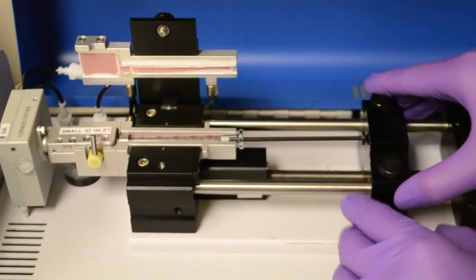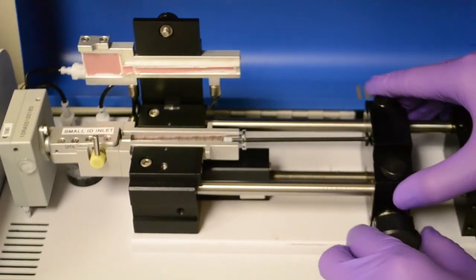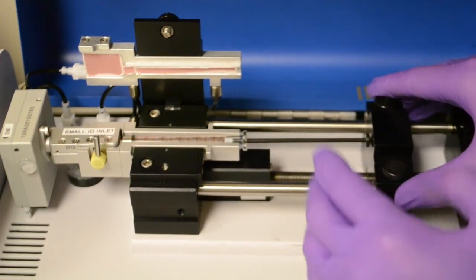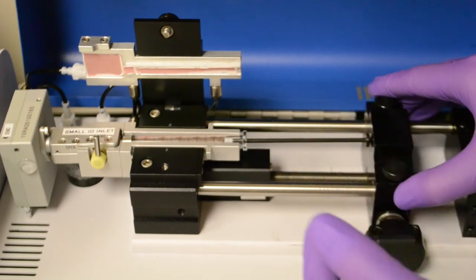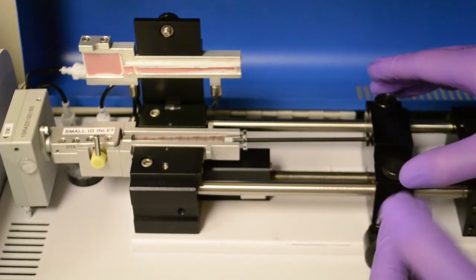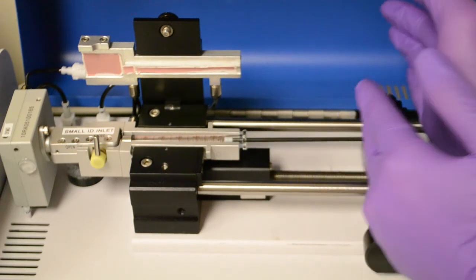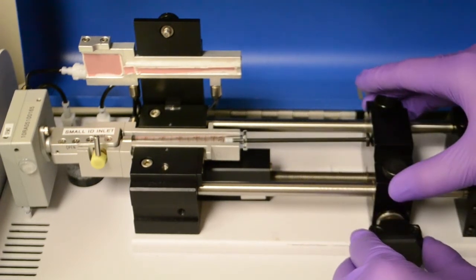And slide the pusher block down gently until it touches. Once you feel the engagement, you may turn the knob to lock your pusher block. Just be noted that the pusher block can only be locked at every full pitch of the lead screw. Sometimes you might have to slide your pusher block away from the syringe a little bit in order to lock it, but that's okay.